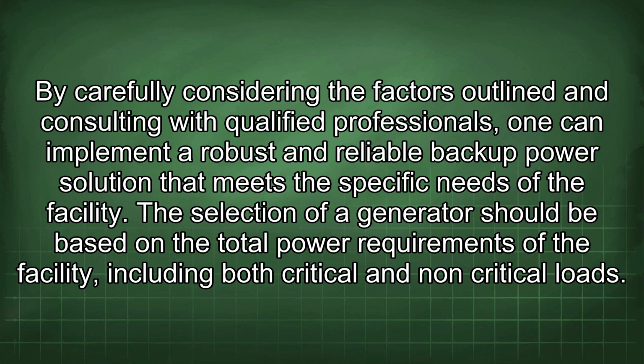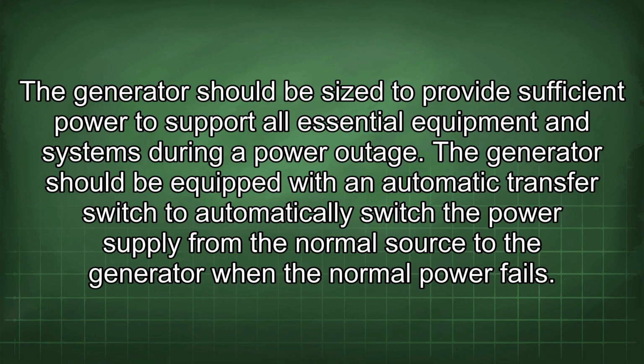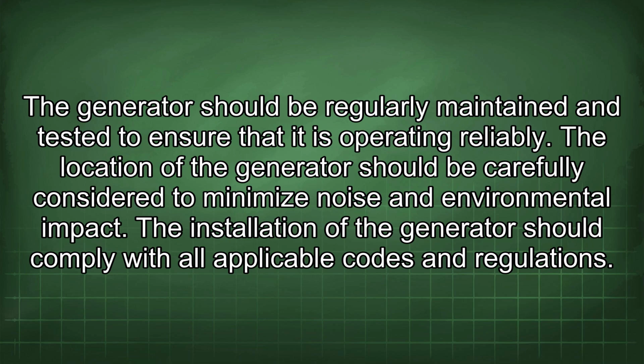The selection of a generator should be based on the total power requirements of the facility, including both critical and non-critical loads. The generator should be sized to provide sufficient power to support all essential equipment and systems during a power outage. The generator should be equipped with an automatic transfer switch to automatically switch the power supply from the normal source to the generator when the normal power fails. The generator should be regularly maintained and tested to ensure that it is operating reliably. The location of the generator should be carefully considered to minimize noise and environmental impact. The installation of the generator should comply with all applicable codes and regulations.